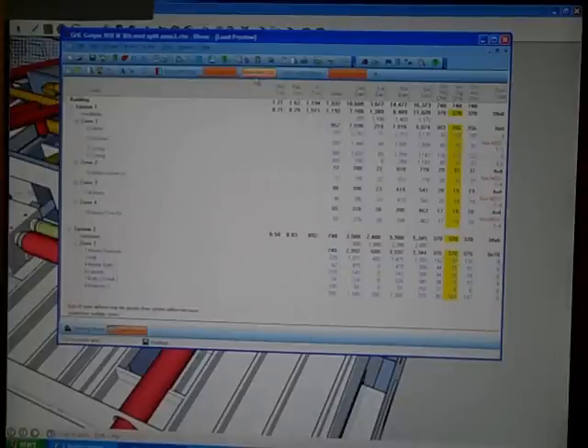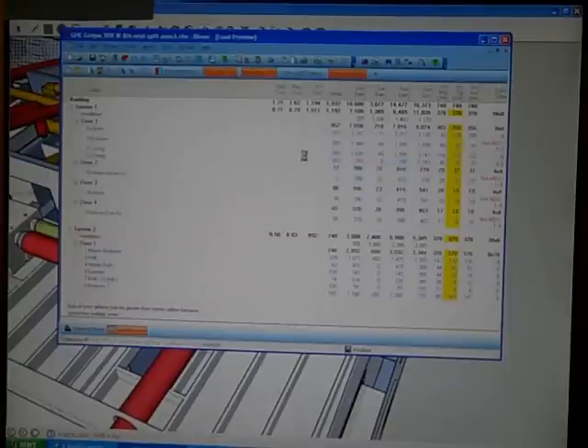You might be surprised to find out how much just rotating a building will change its load. Especially when one of the sides of the house is more glass than the other sides, you're going to see a big difference. You might have a house that one way it sits, it takes 2 tons. You turn it, and it takes 3. So the rule of thumb is not valid.